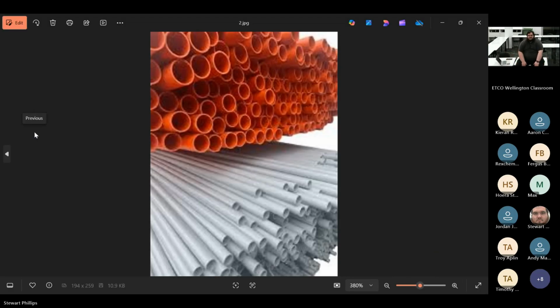Cool. So PVC conduit, what's the difference between the top and the bottom? Color, yeah. What is the color significant? Yeah. Top is underground. Orange is for underground. Orange can be chemically rated, but that's more about wires. Generally we use orange as we consider it ducting for underground, and white or gray or many other colors are for above ground. But if we're using it outside, we need to make sure that it's UV stabilized so it does not wear out under UV light.